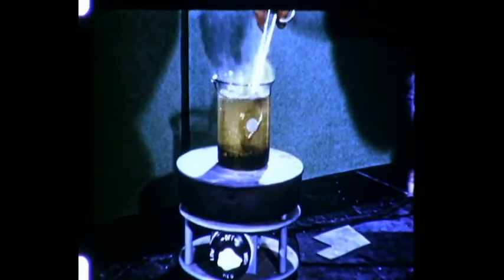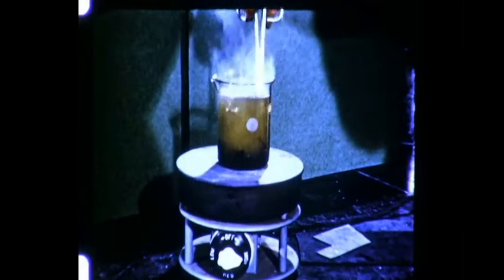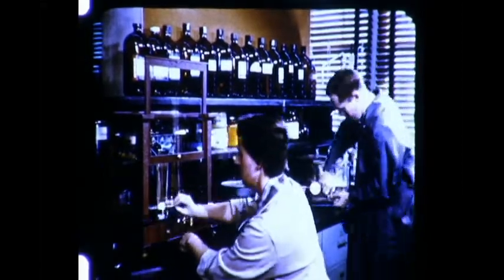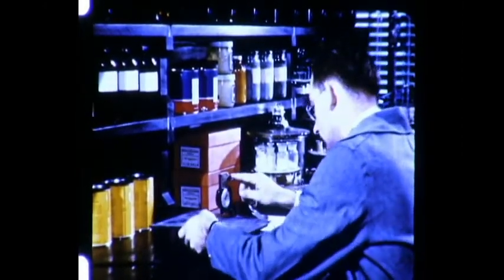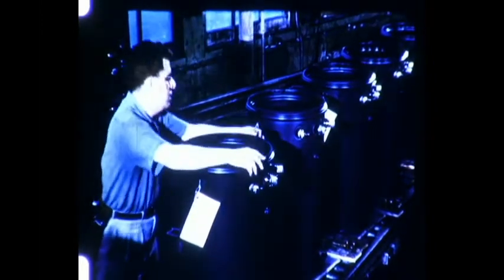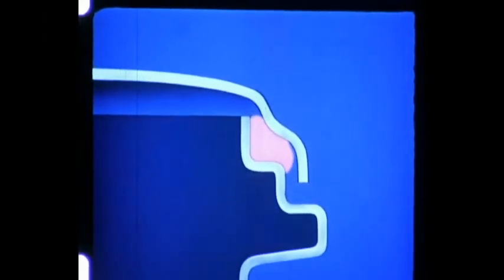But hot transformer oil turned ordinary rubber into jelly in a few days. Here was another problem for the research boys at the Pittsfield lab. For a time, the rubber didn't exist that measured up to the dozen-odd requirements of a good transformer gasket. But we kept plugging, testing everything under the sun, until at last nitrile rubber came along. It gave us a gasket practically unaffected by oil, sunlight, air, dust, and operating temperatures. The gasket is set in a groove and the cover clamped on over it. The back pressure of nitrile rubber fills the joint completely. Even with expansion and contraction, it provides a leak-proof, non-breathing joint — another reason why GE transformers last longer.